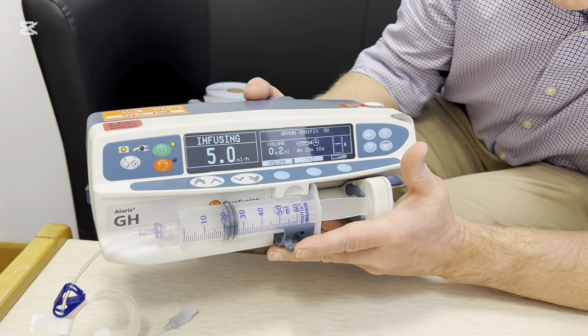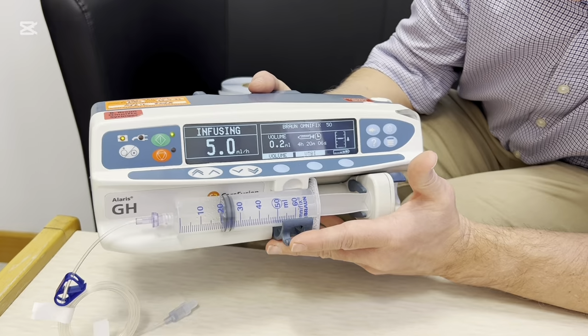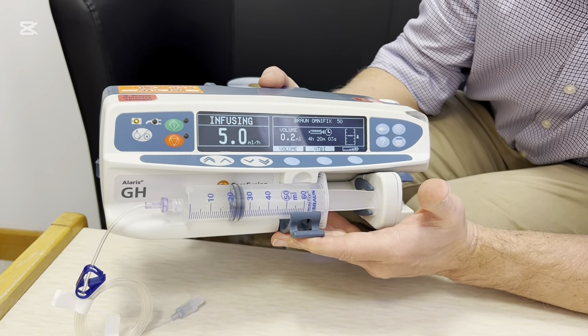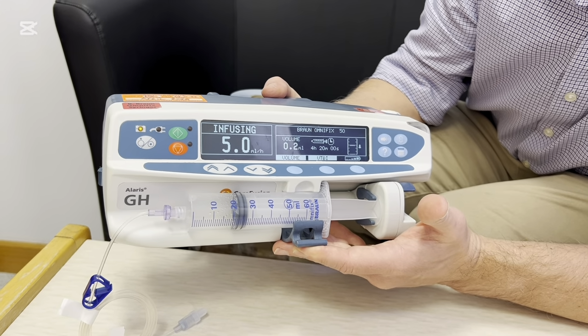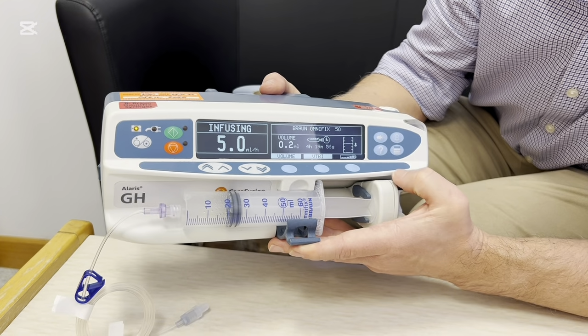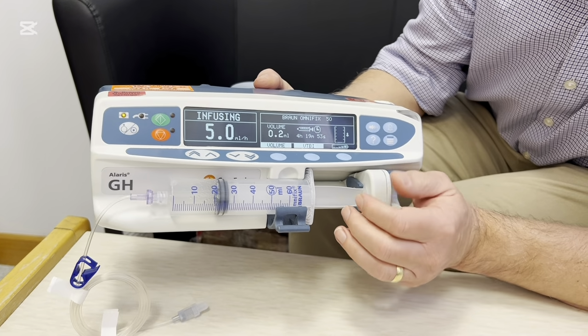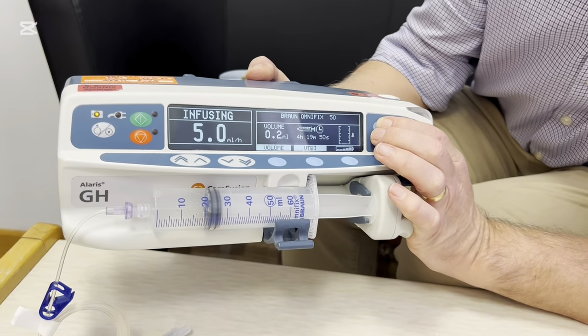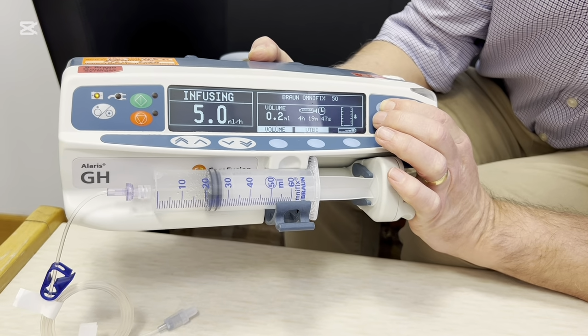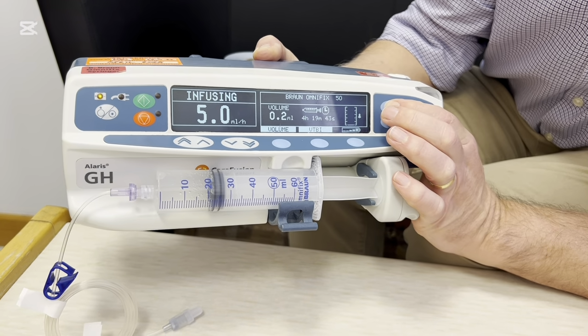If you want to deliver a bolus to the patient under special circumstances, such as you started an inotrope and you need to get the fluid through the central line to the bloodstream, then one of the options you can select is to purge it. This should only be done under very close supervision.